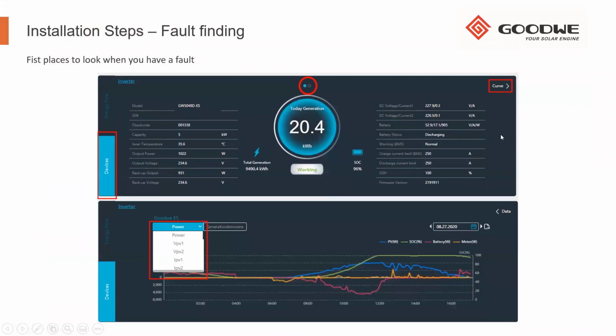So then we move over to fault finding. The first place you can go when you've got a problem, say your customer is reporting their backup is shutting down for some reason, is the SEMS portal on the website. Below we'll see the energy flow, and then we have the devices tab. In the devices tab, if you've got multiple devices on the plant, you can select them here individually. You'll see an arrow here to scroll through the different plants.